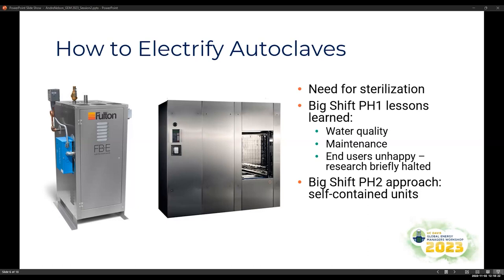We ran into a lot of water quality issues, which led to failing boilers. We also underestimated the maintenance load that these extra boilers would put on our steam shop staff, because they actually have to go out on site every single day to blow these boilers down and maintain them.